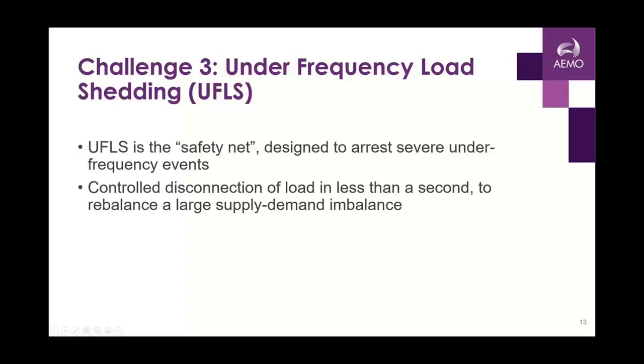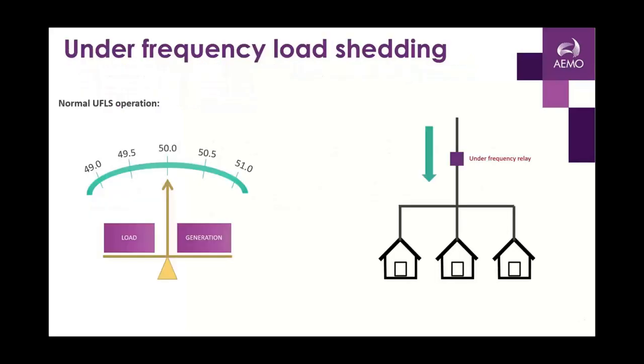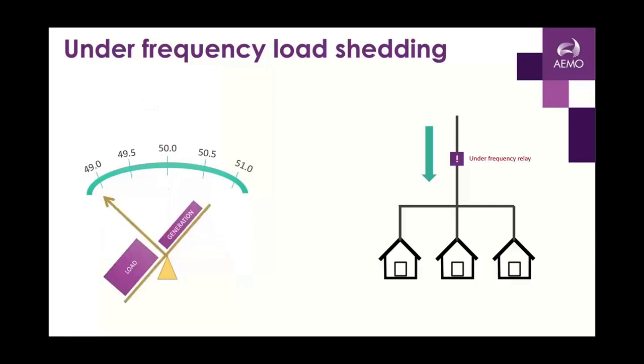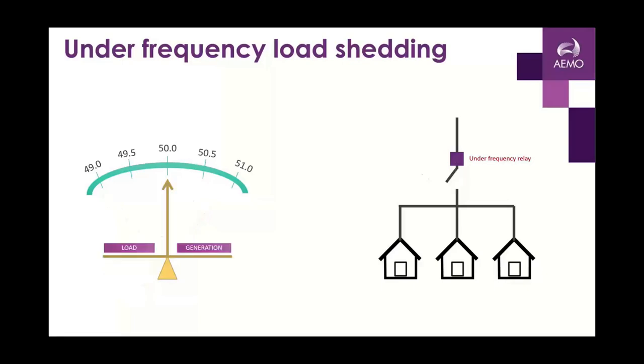The third and final challenge is our under-frequency load shedding. I mentioned this before, but it's effectively our safety net designed to arrest severe under-frequency events. So if our frequency is really low, we are able to do a controlled disconnection of load in less than a second to rebalance a large supply-demand imbalance. This is an example of what that would look like. We have all these loads, and when we see the frequency go out of the range, we can open a switch and disconnect all of those loads, so that we can correct our load and demand balance once again.